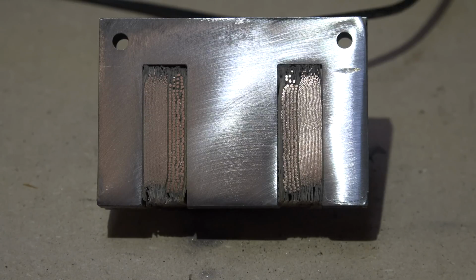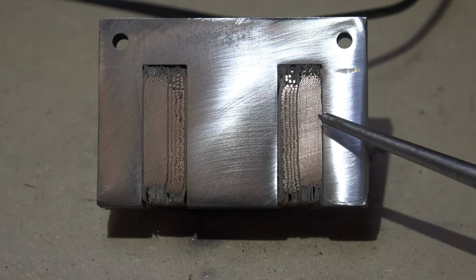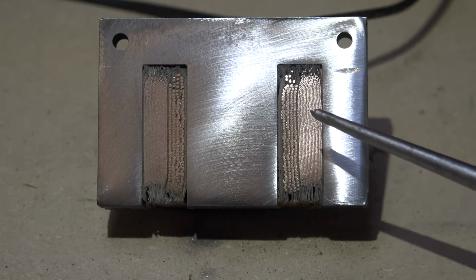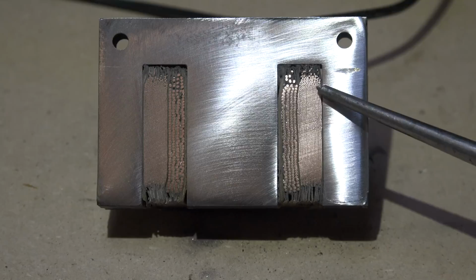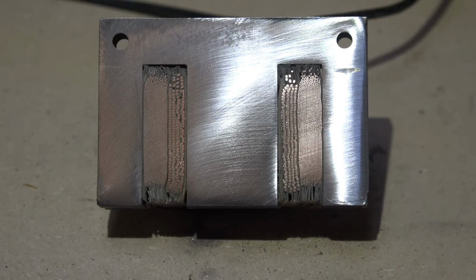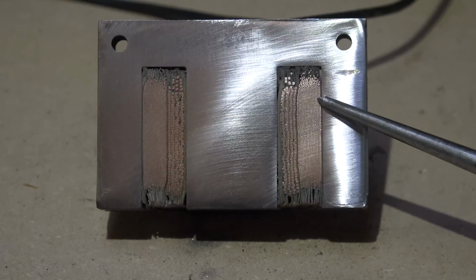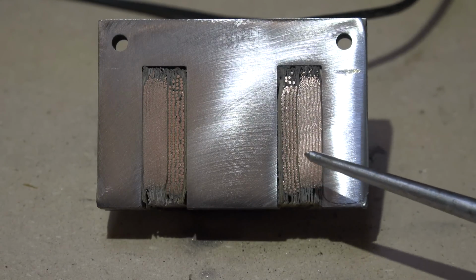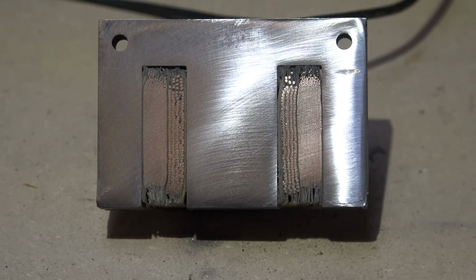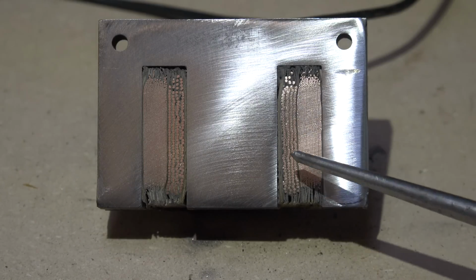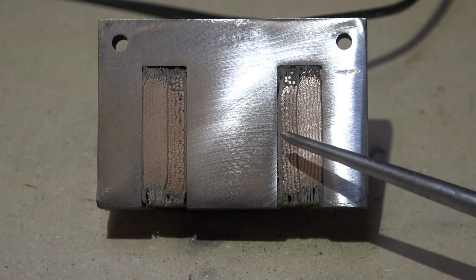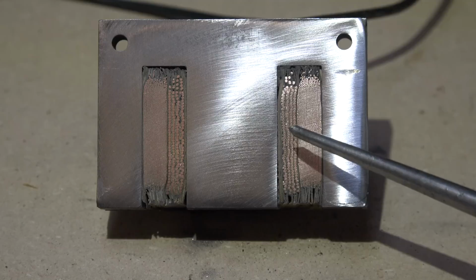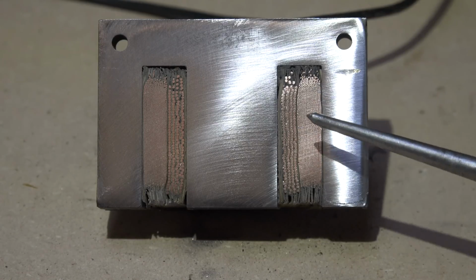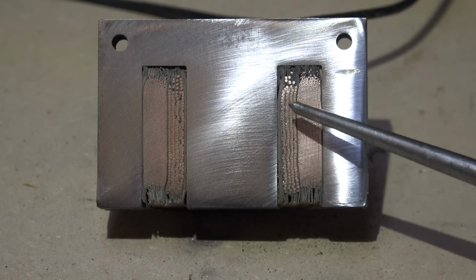What I want to point out here is we've got two sets of windings. We've got this set of windings here, very small wire. That's the 240 volt, because this is a step down transformer. Remember, 240 to 24, 1/10 of the voltage. So I have all these windings here, quite a number of them. And then I've got these windings here. Now that's the secondary, that's the 24 volt. There's a lot more windings in the primary than there is in the secondary.